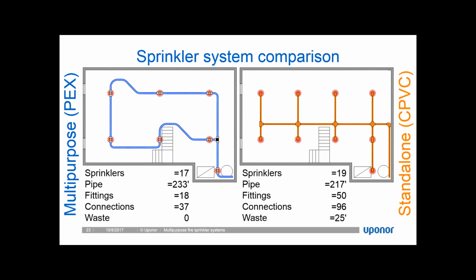The other factor that we're not looking at, that I alluded to earlier, is size. Because the hydraulics work so unusually on a tree system, I can't get down to a small pipe size across the board. So depending on what my incoming water pressure is or what my design configuration is, I may be installing 1.5 or 2-inch pipe for some of these main lines. But that's nothing I can compare unless I'm doing a hydraulic calculation, and we don't have enough time for that today. It's not very interesting anyway, so I'm saving you guys a lot of headache.